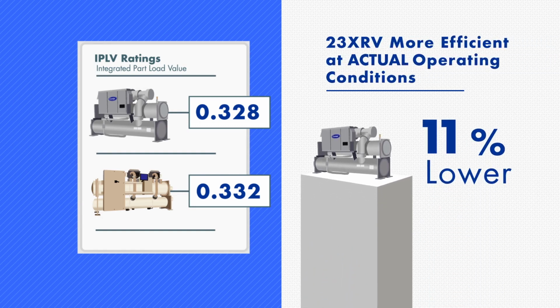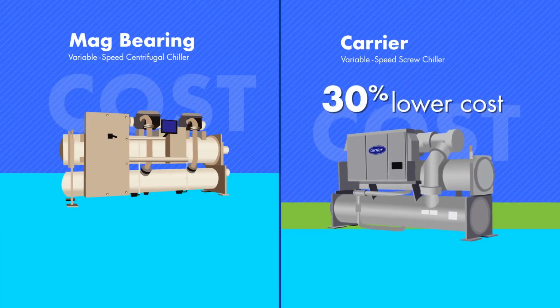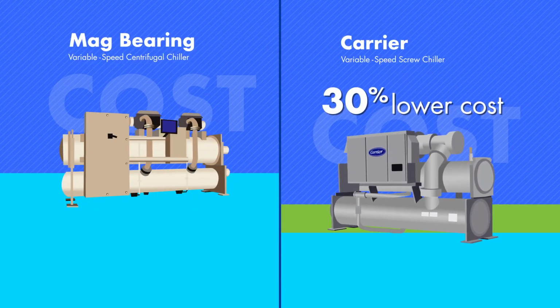The Carrier chiller had an energy consumption rate that was 11% lower than the mag-bearing chiller, significantly more savings than submittal data would indicate. It's also worth noting that these savings are on top of a Carrier chiller equipment cost that was more than 30% less than the mag-bearing chiller with the same cooling capacity.